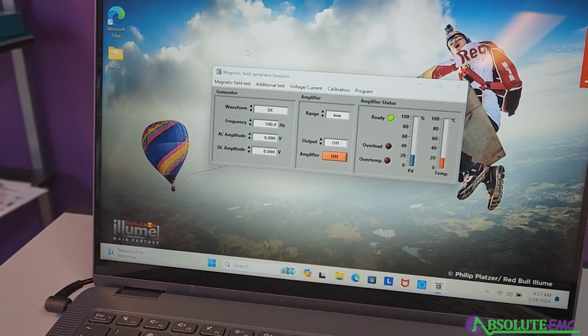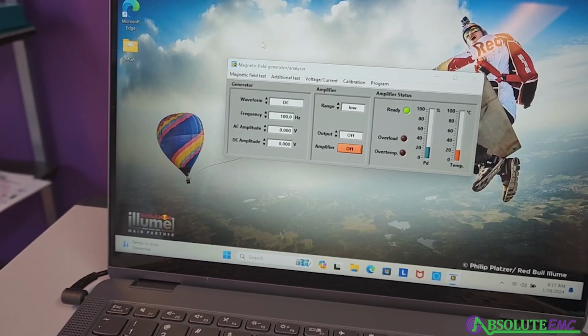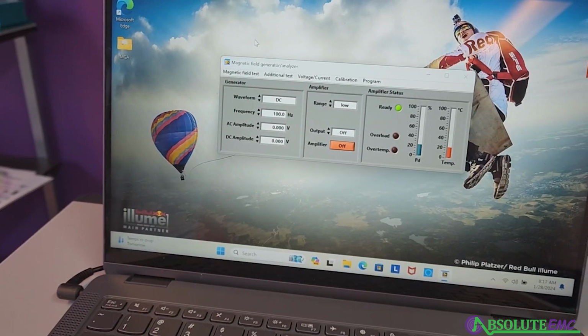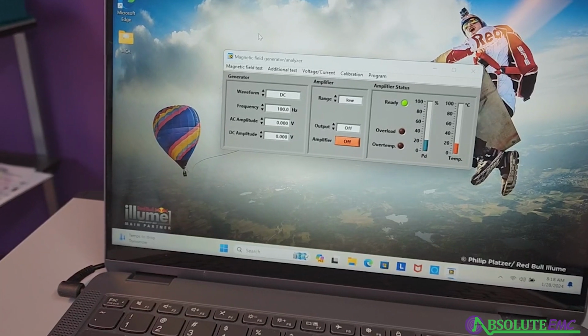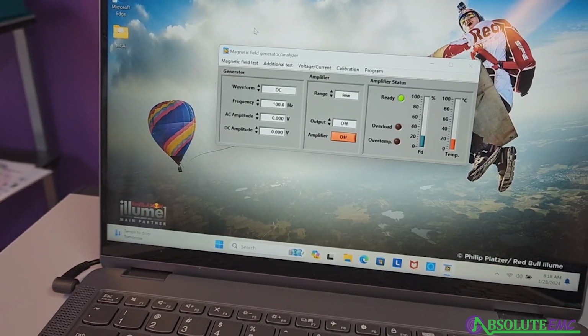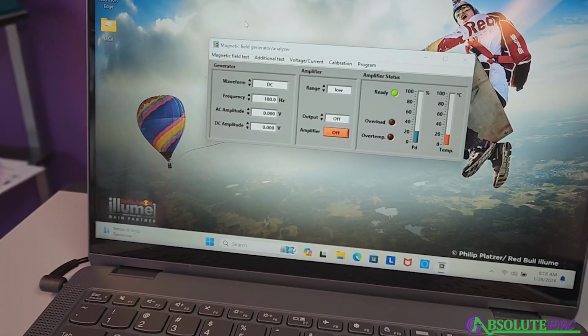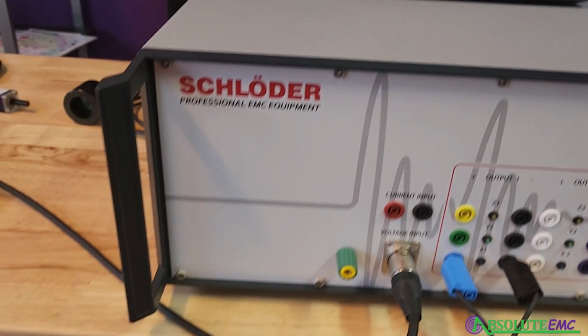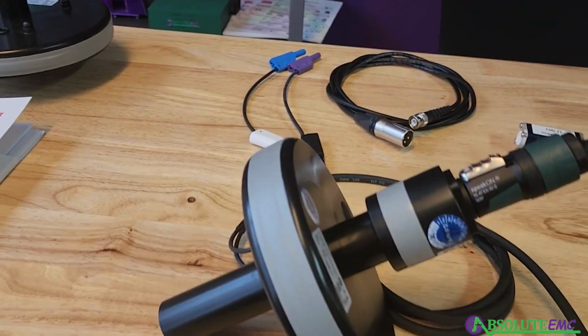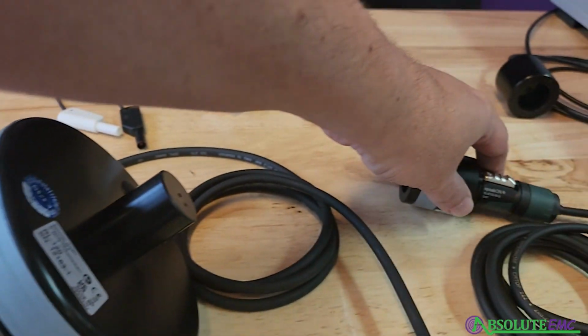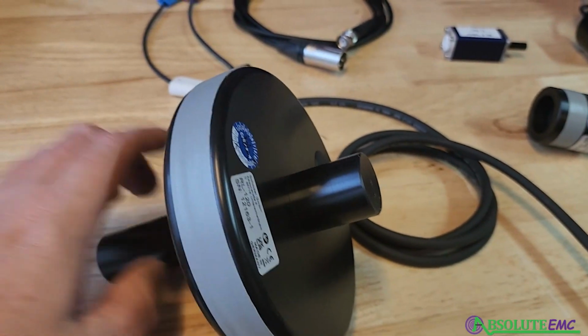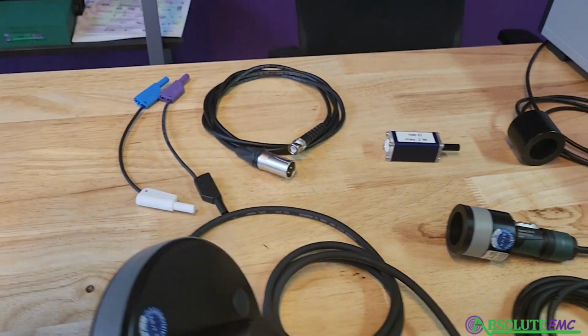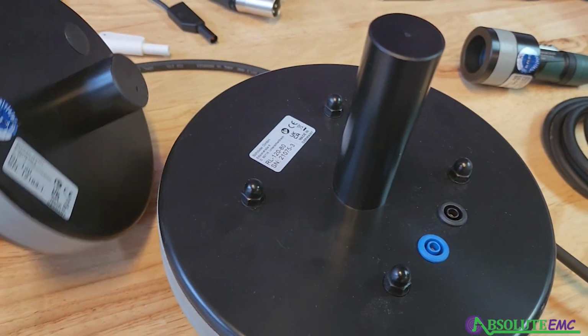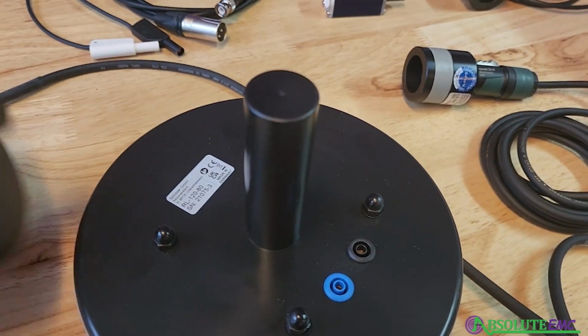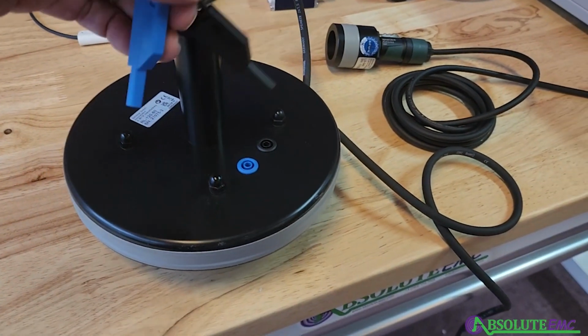Now we're going to show how to run a test for a single frequency at a time. This is normally used for the low frequencies when you have to dwell for a little bit of time. You can do one frequency at a time in the DC range and low frequency hertz. So to do that, first we're going to change the setup a little bit. So right now we have the higher frequency loop and loop sensor hooked up. What we're going to do is switch to the larger loop. Let's move the connections over.